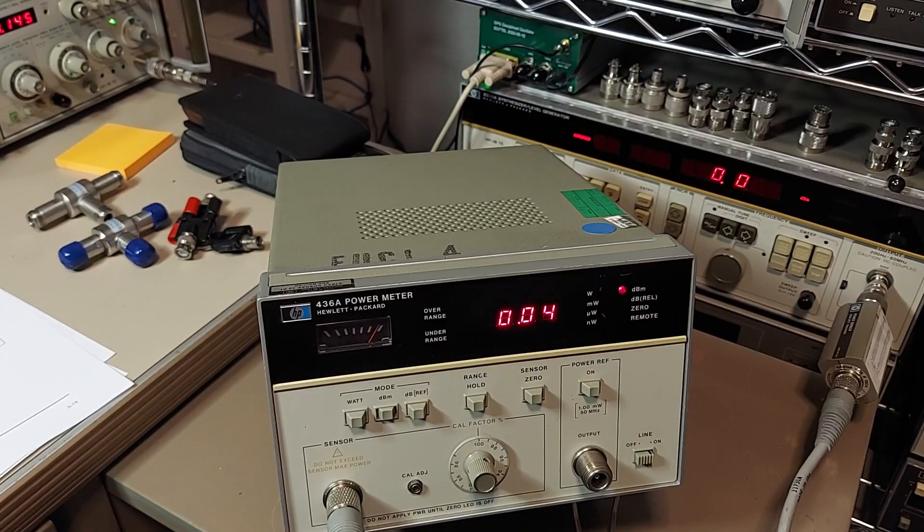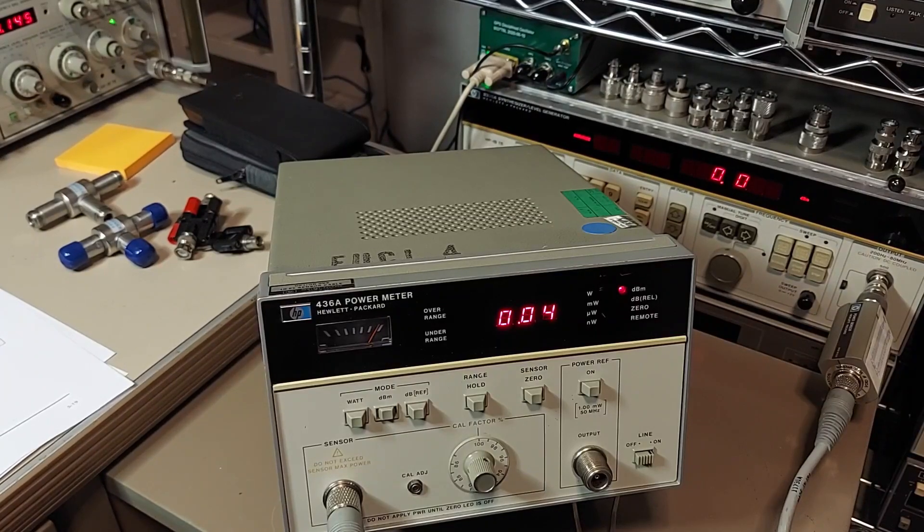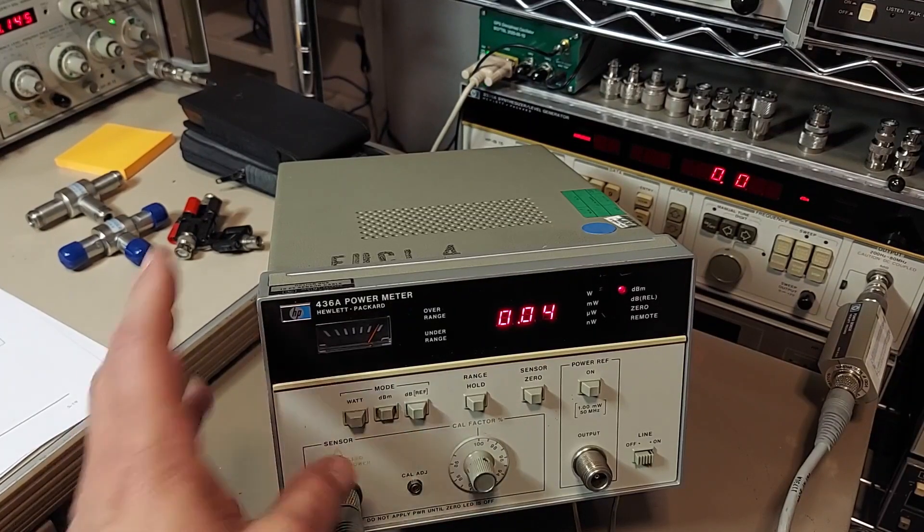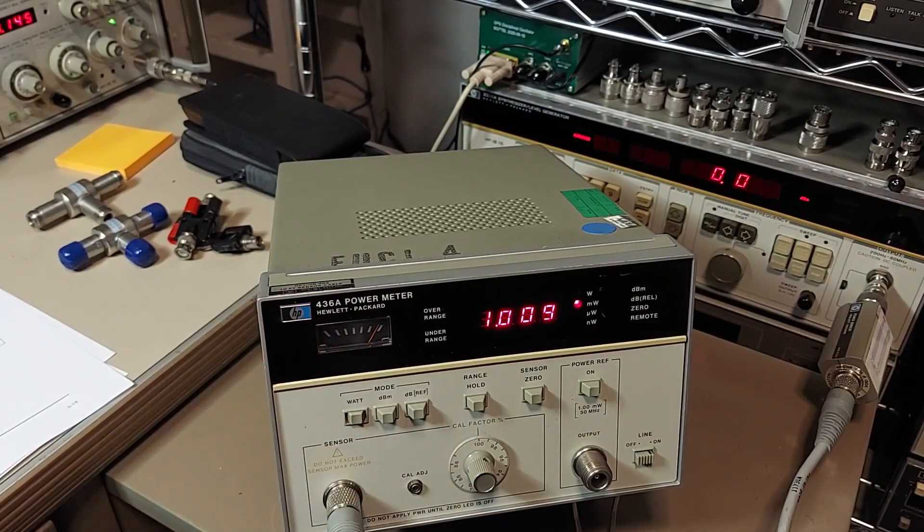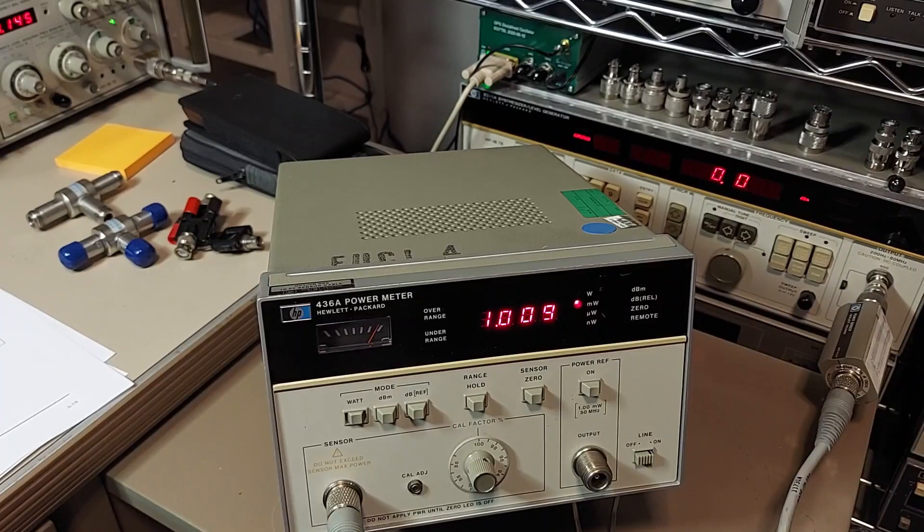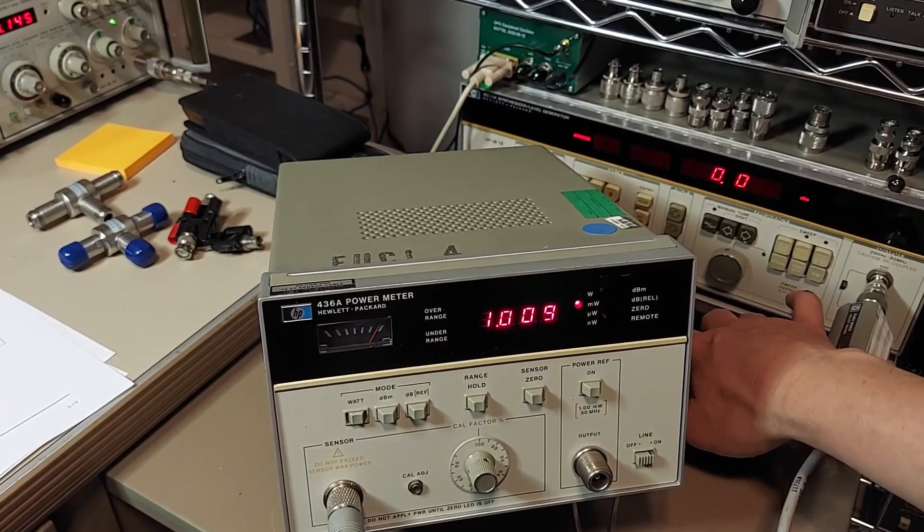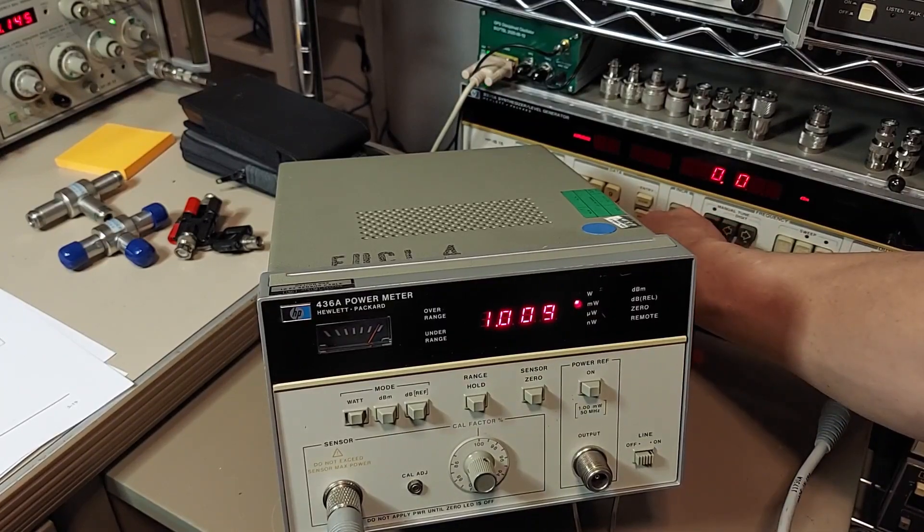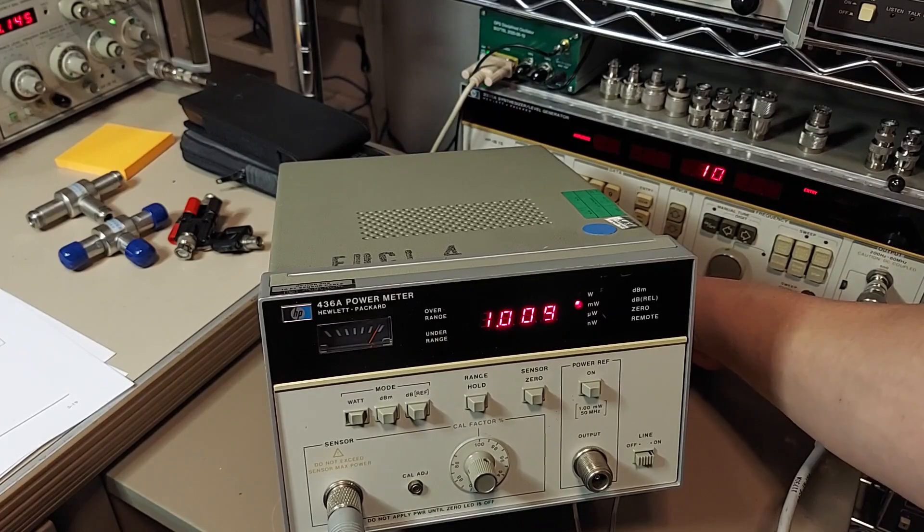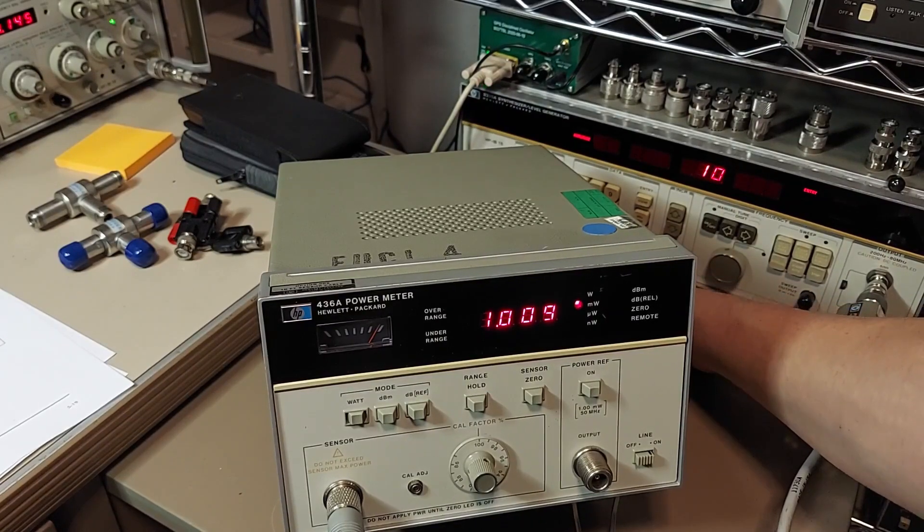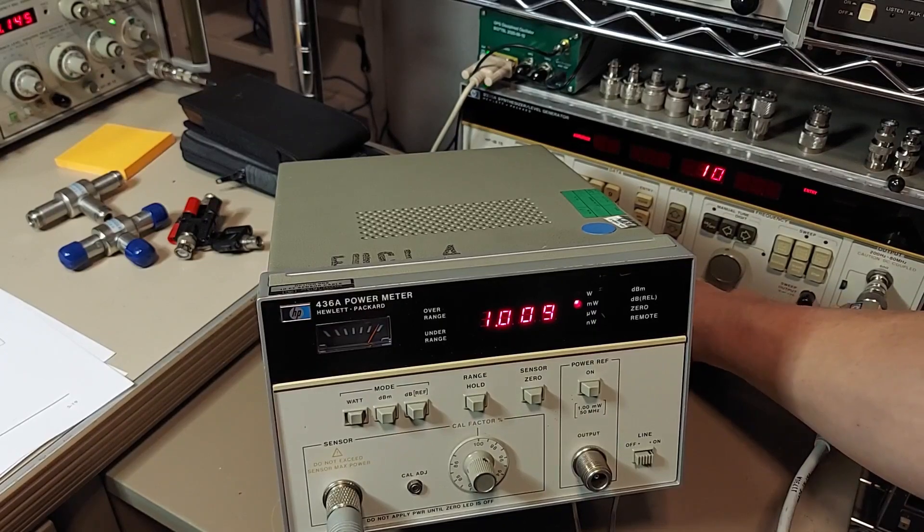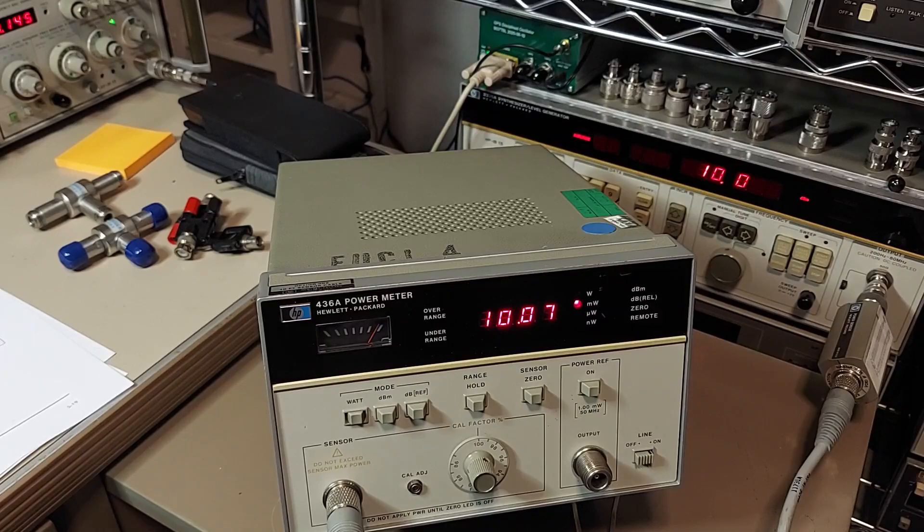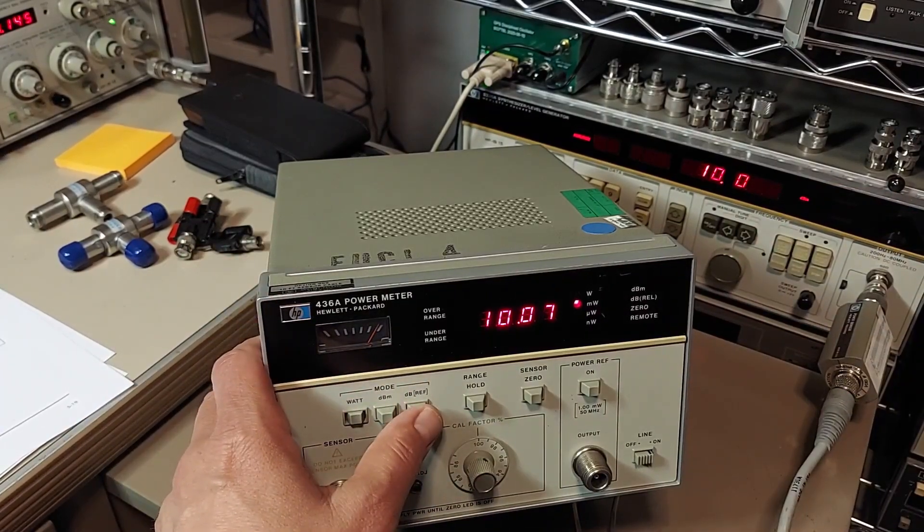But I just forgot, so before we open it, I wanted to show you the couple of buttons here. We go to watts here and it'll show you the amount in milliwatts. So we can go to, let's say, 10 dB, which should give us about 10 milliwatts. There we go, yep, 10.07 milliwatts.